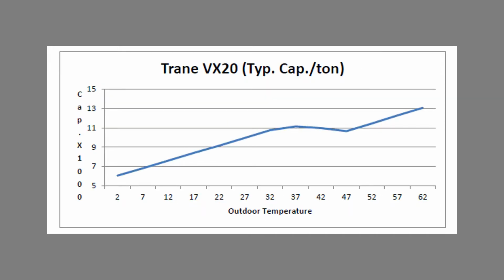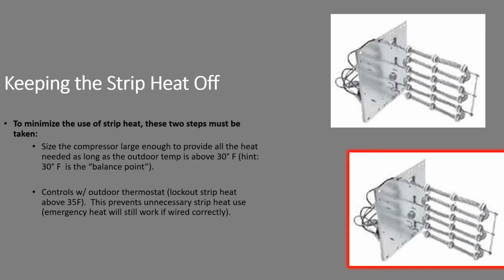Here's another system that's an extended capacity system. It's a little flatter. This one does have higher capacity at warmer temperatures, but notice this very flat spot here, roughly between 27 and 47. That's sort of where we live in the Northwest, so your capacity remains flat through that temperature range. Keeping the strip heat off, how do we do it? We size the compressor large enough to provide heat for the house all the way down to 30 degrees. 30 degrees is a balance point we like to see.